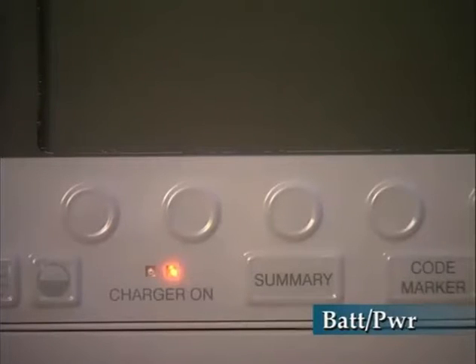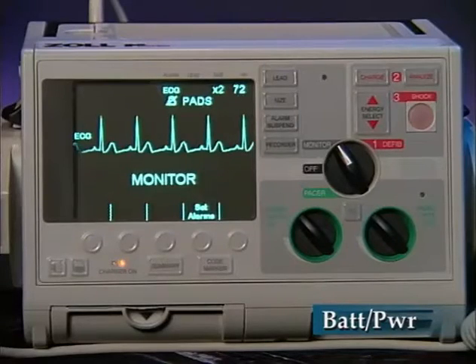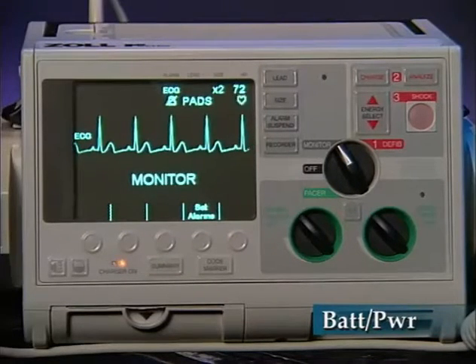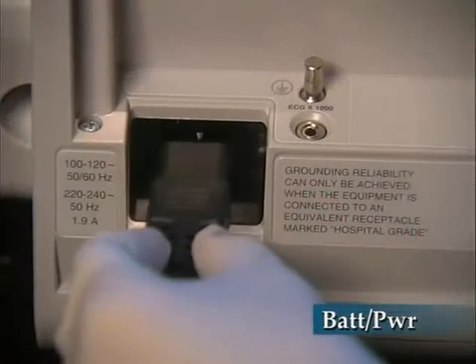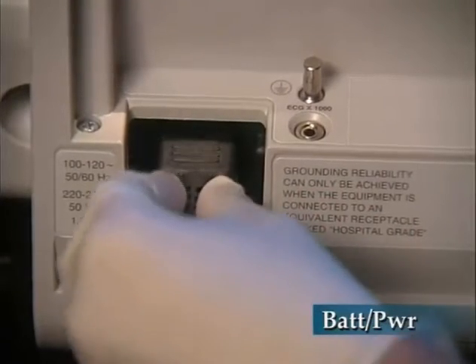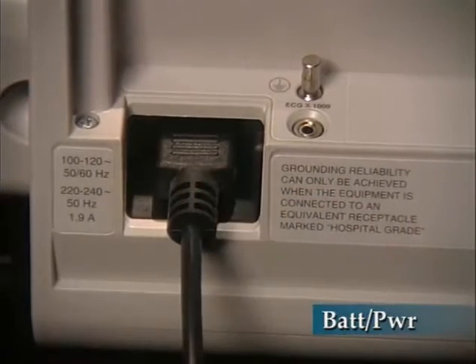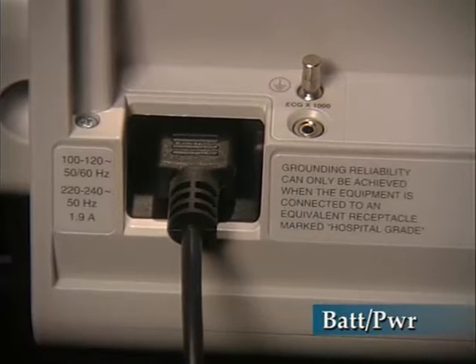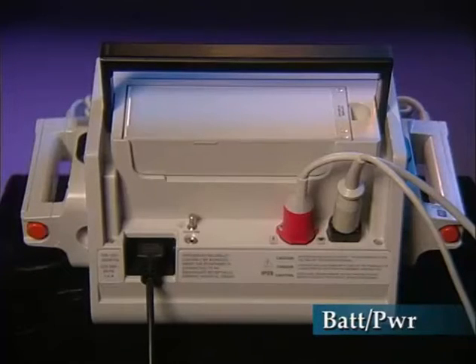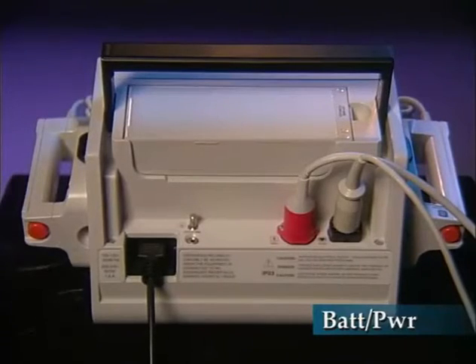With an M Series connected to AC or DC power and turned off, the unit will fully recharge the battery within 4 hours. If the unit is on continuously, recharging will be complete in 24 hours. If equipped with AC mains or DC capability, the unit will operate regardless of battery condition or without a battery. The power cord must be connected to the device and a suitable power source for charging and operation.